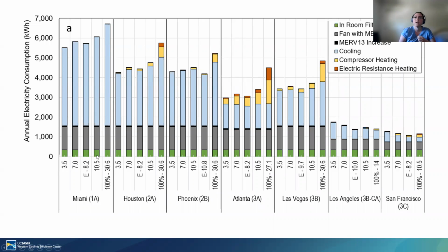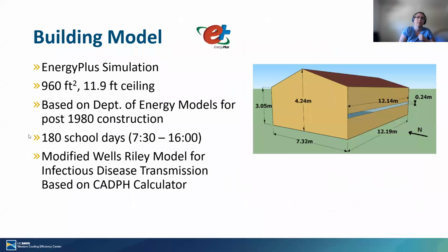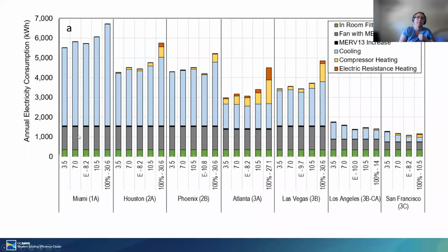I also have here the energy use from a portable air cleaner. You can see it's pretty small. And then we have the energy use from the HVAC fan, and this tiny, tiny little black bar, that's the additional energy used by a MERV 13 filter compared to a MERV 8. So just having the fan and the MERV 8 filter, like any filter, just the fan system itself, moving the air through all that ductwork, it's a big chunk of the energy use in a classroom. And if we just upgrade that filter and we have a little extra resistance, we just use this tiny amount of energy. So the MERV 13 filter is just really good bang for the buck.